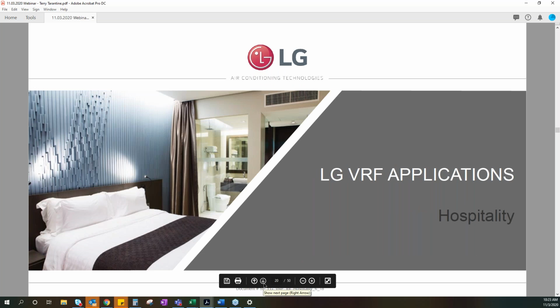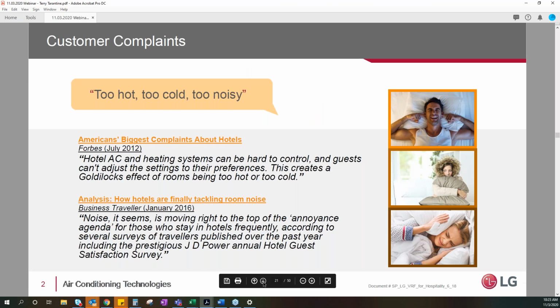I grabbed this application because it's something that we're seeing a lot of in our market, and that is the hospitality side. And this goes not just for hotels, but we're also seeing this in office buildings, where one of the advantages VRF has over all the others has been on the noise side, the sound level. When rooftops start up, when water source heat pumps start up, and especially PTAC units in hotels start up, they're very noisy, or they can be very noisy.